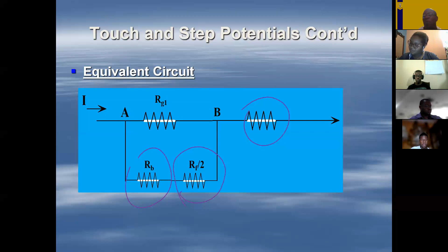For the step potential, we are being normal, we are walking around. So in stepping or walking around in the substation, we then have a portion being tapped off, separated by our feet. We have the two feet resistances, RF and RF, and we still have the body resistance. The idea is what will flow through our lower body from one foot to the next while we are walking around, because only your feet would have been connected to ground. So for this, the equivalent circuit looks like that, but as I said, the equivalent circuit is not our focus, nor is the drawing.